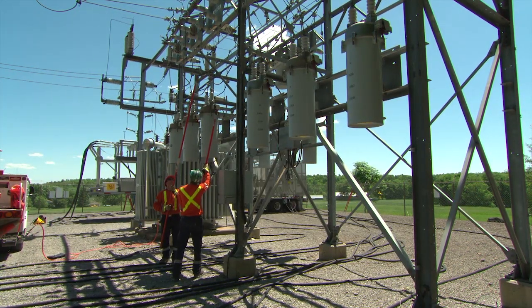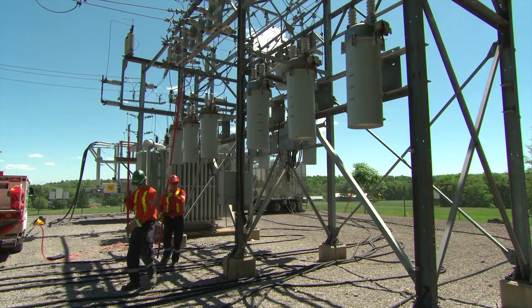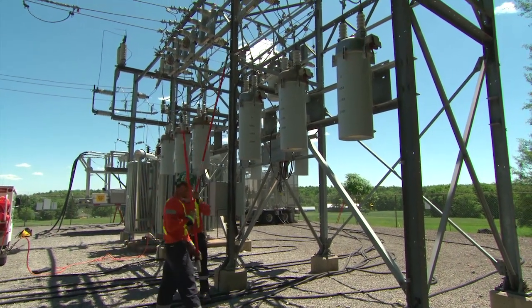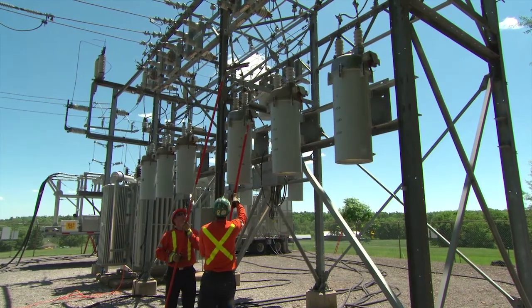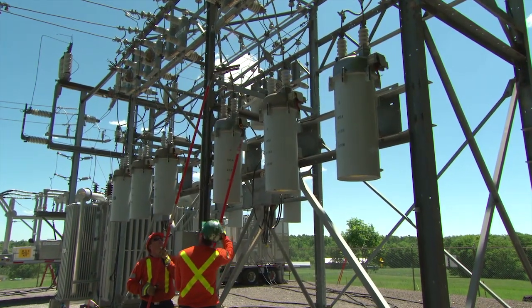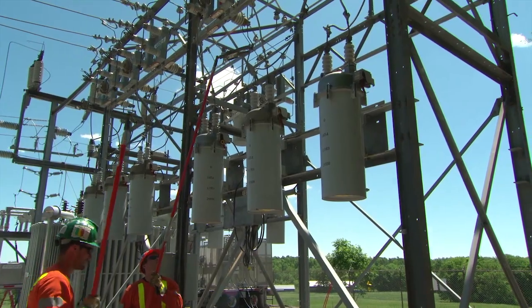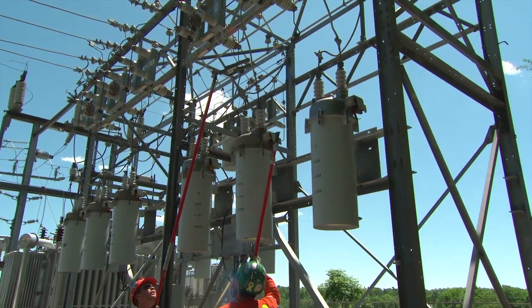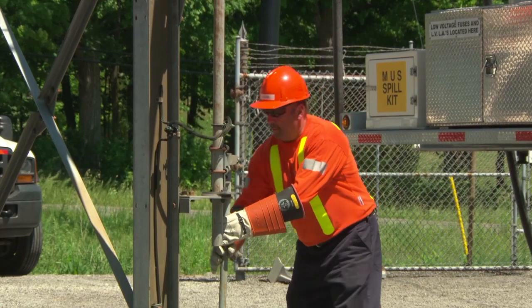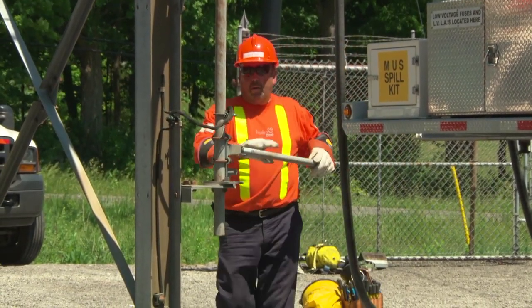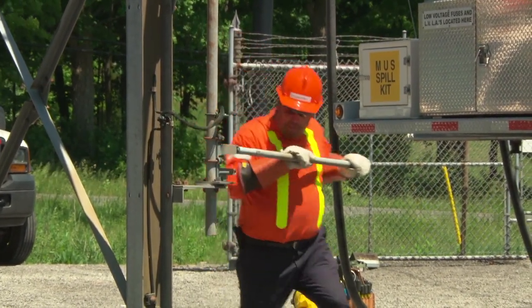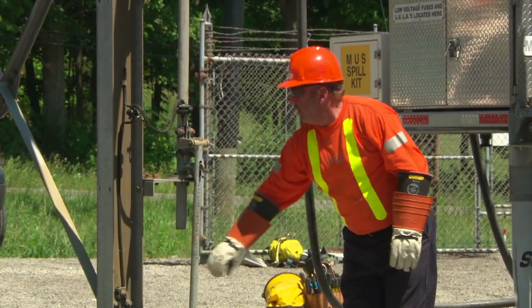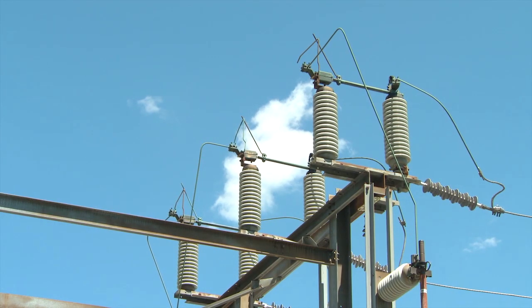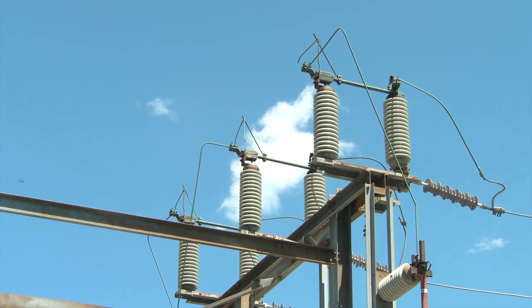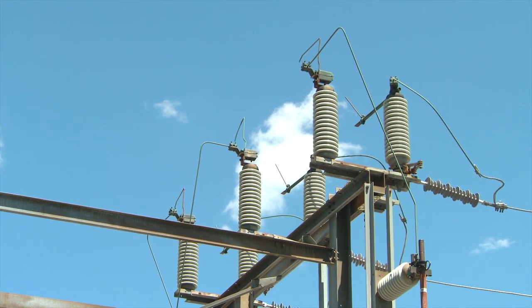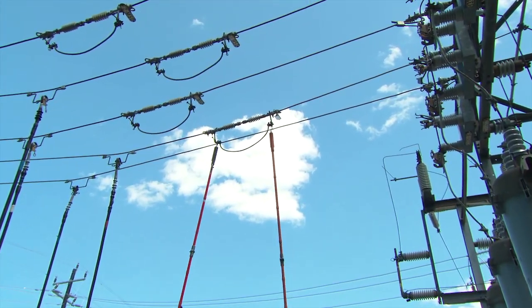Open the station reclosers to break parallel between the MUS and the DS. While doing this, another RME is measuring the feeder current with an amp stick ammeter to ensure that the reading goes to 0 when the recloser is opened. Open and lock the station high voltage disconnect switch to take the station off potential. Surrender the hold-off on the high-voltage circuit.